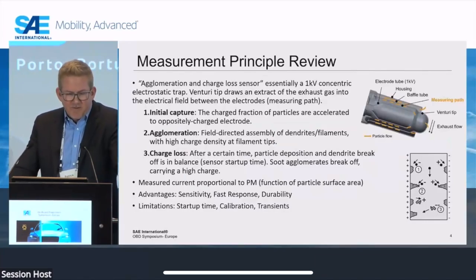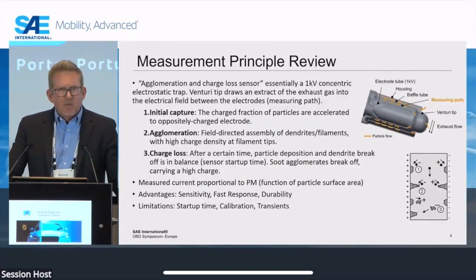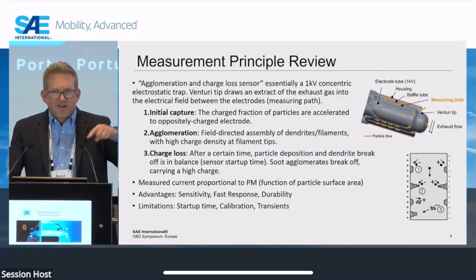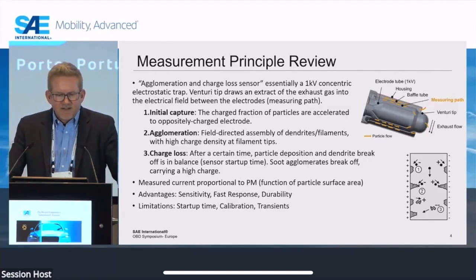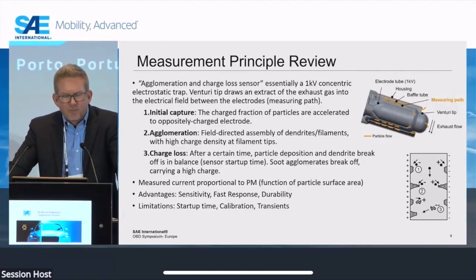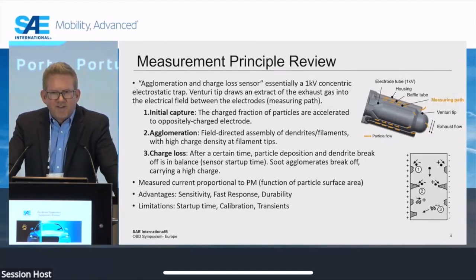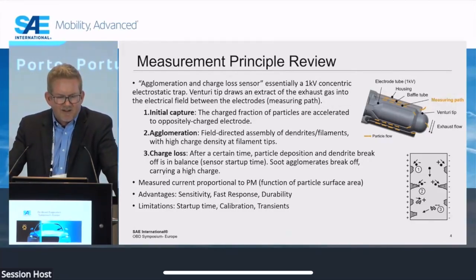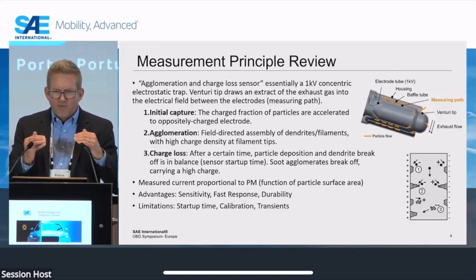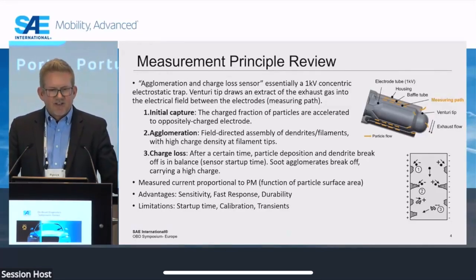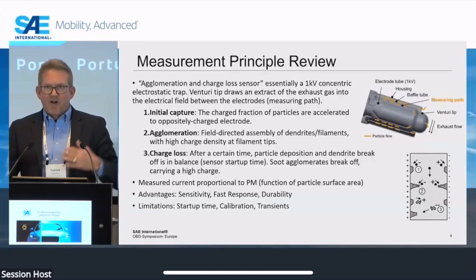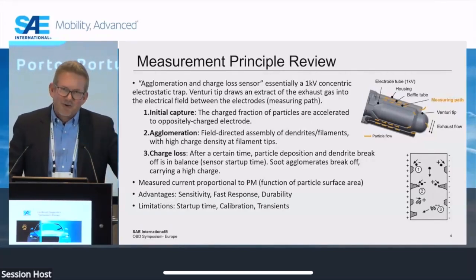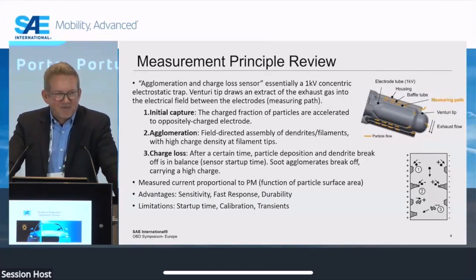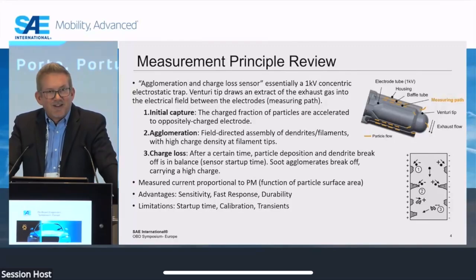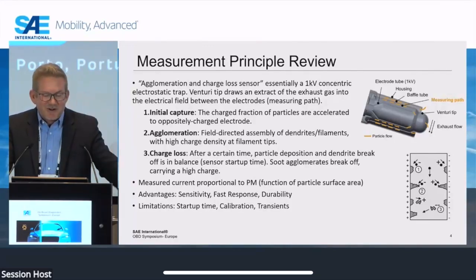So, a quick review of the measurement principle. This is essentially a 1 kilovolt electrostatic trap, right? So concentric, as if you picture an inner electrode and then a concentric outer electrode, exhaust gas is drawn in through the electrode by a Venturi tip, using the exhaust gas velocity itself to create the vacuum. The 1 kilovolt field does essentially field directed assembly. The positively charged particles are attracted to one electrode and the negatively charged particles are attracted to the other electrode. By the way, the neutral particles don't participate in the measurement. So that'll be one of the things we talk about today.